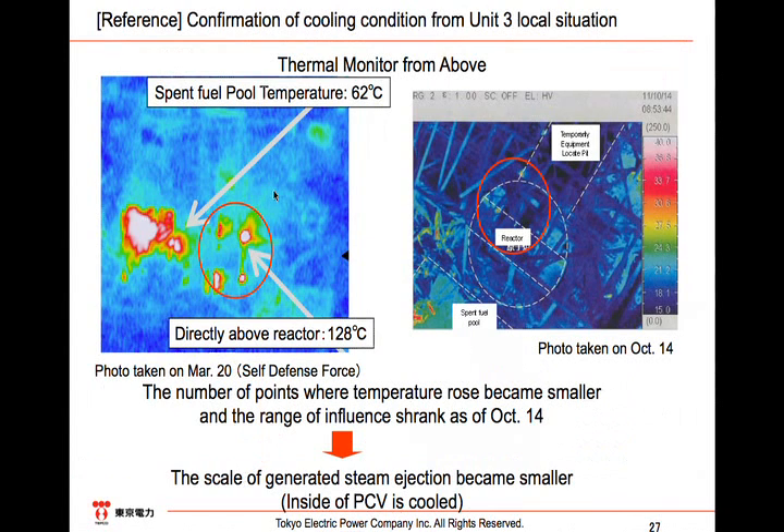As for Unit 3, no direct photographs were taken. The temperature above the reactor was 128 degrees through the thermal monitor on Mar. 20, but on October 14, the areas of temperature increase became smaller. Hence, we believe that high temperature steam is not leaking from the PCV.